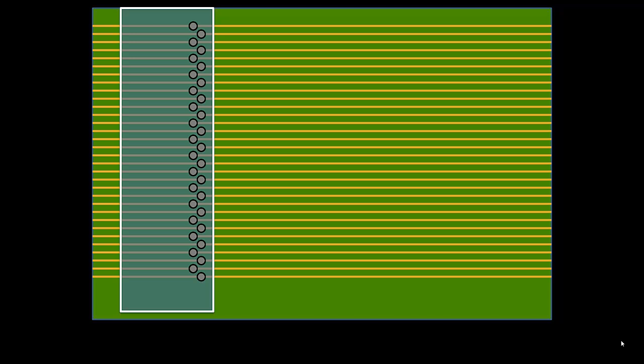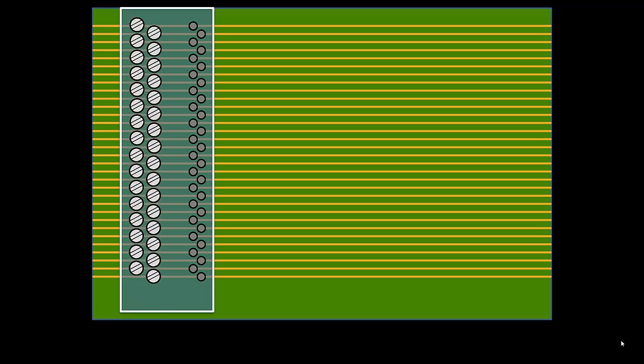Next we'll add some terminals so we can connect to the outside world — you could say these screw terminals are for field devices or field wiring. Since we are adding these connections to connect outside devices into the copper traces on the backplane circuit board, we will call this an input interface. Because we're going to make it removable — you can plug it in and unplug it — we'll call it a module: our input module, an interface between the outside world and the backplane.